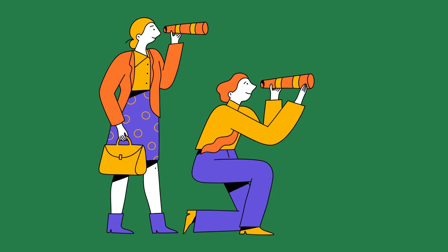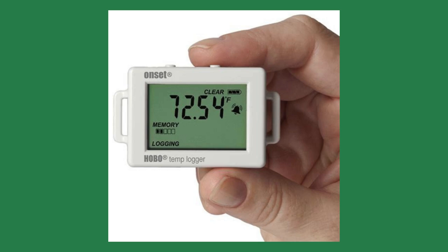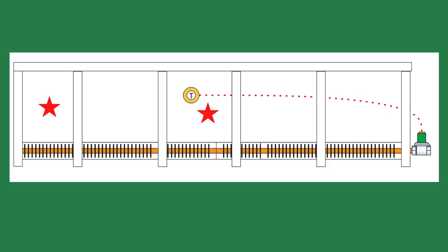To satisfy my curiosity, Marianne and I went inside the office with the thermostat after everyone left to check for a heater. Just as Marianne suggested, there wasn't a heater. My suggestion to Marianne was to place a couple of temperature data loggers in the offices to trend the temperatures, and she agreed. A data logger was placed in Mrs. Williams' office with the thermostat and one was placed in the office at the end of the piping run.